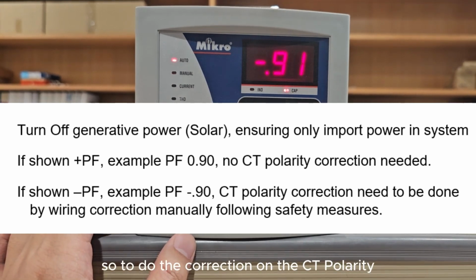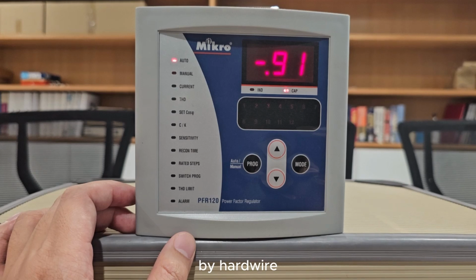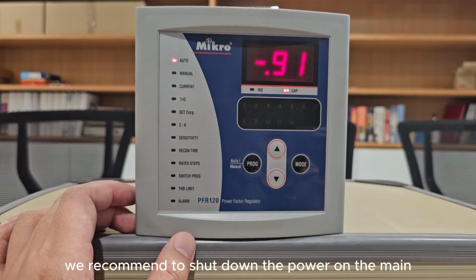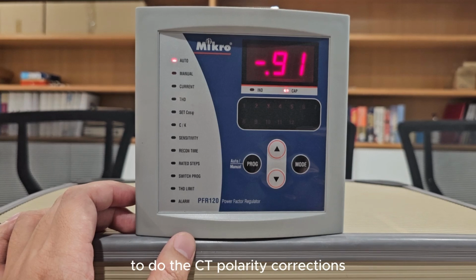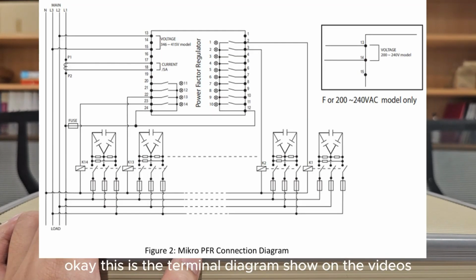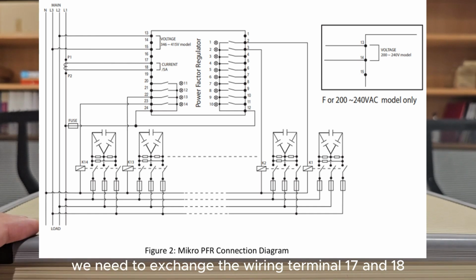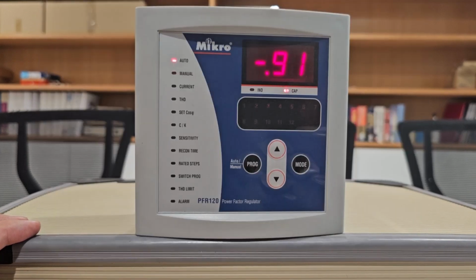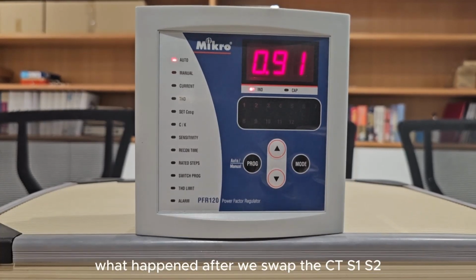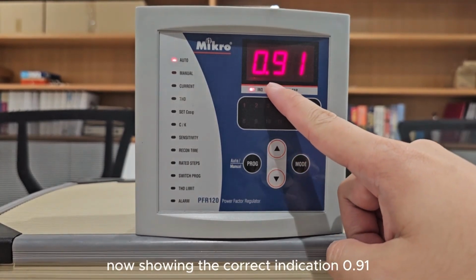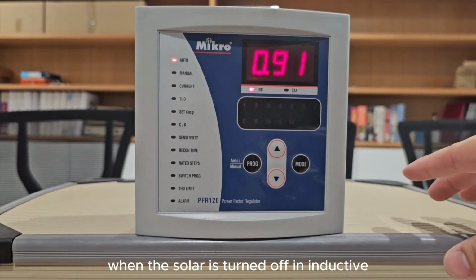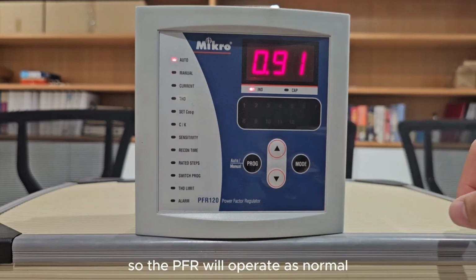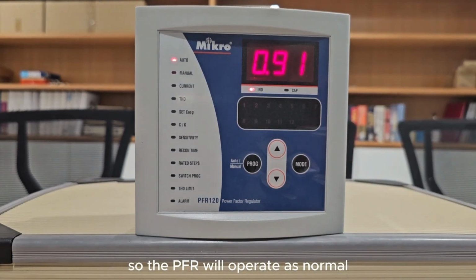To do the correction on the CT polarity by hardwiring, we recommend to shut down the power on the main. Okay, this is the terminal diagram shown on the video. We need to exchange the wiring terminals 17 and 18. So this is what happened after we swapped the CT S1 S2, now showing the correct indication 0.91, which is import power condition when the solar is turned off, inductive. So the PFR will operate as normal.